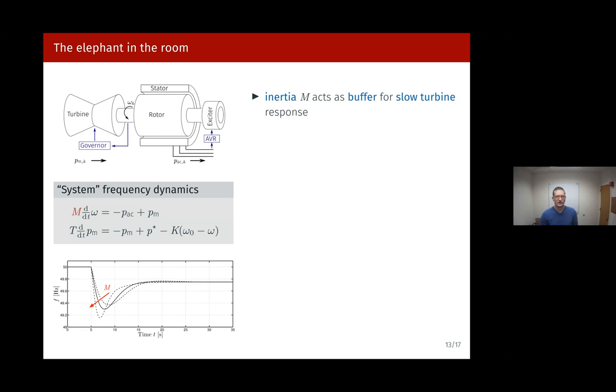So before moving on, here's one of the things I have not talked about, and this typically comes up in all of these presentations. Okay, so what about inertia, right? We're losing inertia in the system, and what everyone keeps telling us is that our frequency response to a load step, as we decrease the inertia, will do something like this here, right? And I was telling you that, under these control laws, you're basically exploiting the energy buffer of the power converters, and that's more or less negligible.